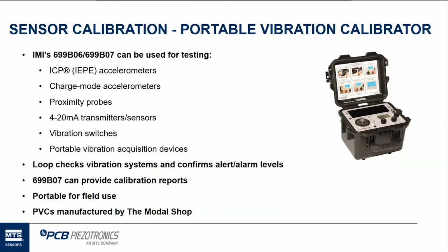This can also be used to do loop checks on vibration systems. So if you've got a vibration monitoring system with alarms set, you can hook this calibrator up to test those alarm levels to make sure they're working where they're supposed to. Alarm levels, trip levels, all that can be done with this.